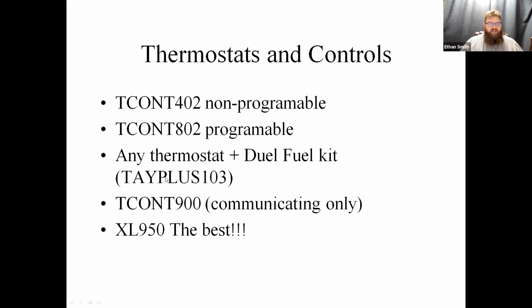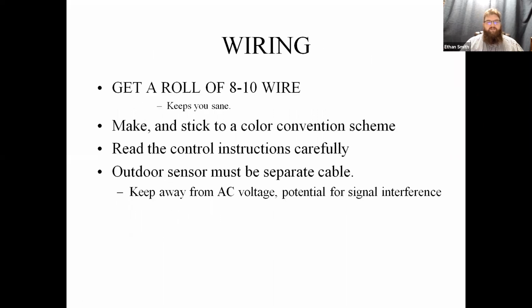So this little kit here, this TAYPLUS103, is that old mechanical dual fuel kit that was out there. We still see these things out there. I had a contractor that was installing them as recently as 2 years ago. So that's that mechanical switchover. Now we're getting into the communicating controls and the solid state controls. It's all different. But if you're going to run a 24 volt heat pump system, I would recommend you get a roll of 8 to 10 strand wire.